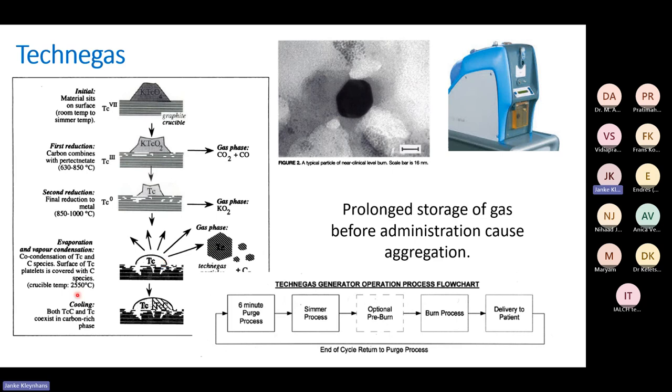The system cools after reaching temperature. It's really important to follow the process: purge, then simmer process, pre-burn, burn, and then deliver to the patient. If there is too long a waiting period after manufacture, the particles combine to make larger particles and grow — they will no longer be nanometer in size, giving a less optimal imaging procedure. Always follow the manufacturer's steps and don't let the preparation stand too long.